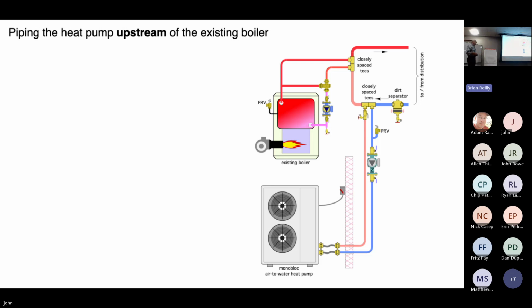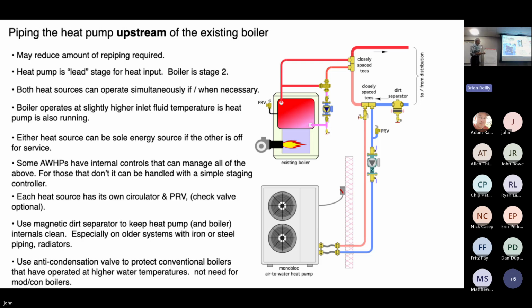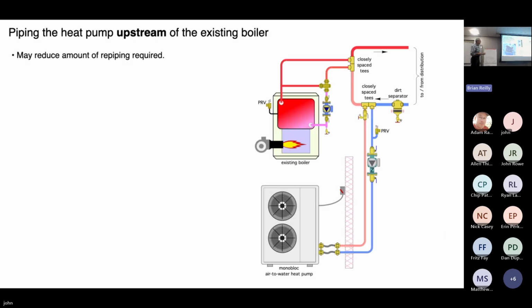When would you use this? If it simplifies the modification of the system piping. If you've got existing piping and you're trying to do what I call the least invasive surgery on that piping as you add the heat pump, this is an acceptable way to try to minimize that modification of the piping.